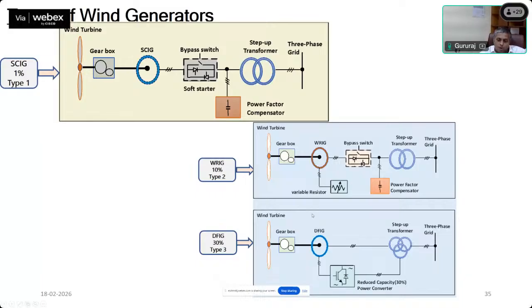So then the most important type of generator, what we call a type 3 generator, is very widely adopted, even in this country. Suzlon, one of the top manufacturers, has plants across the country, and if you go to their website and see, the 2.1 megawatt standard DFIG, doubly fed induction machine, is what they have installed at various places. So what is the specialty of this doubly fed induction machine? You see there are wind blades connected to a gearbox, and it's coupled to the doubly fed induction machine. It's a slip ring induction machine.